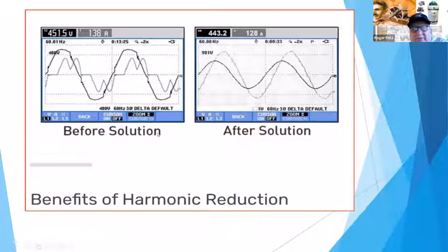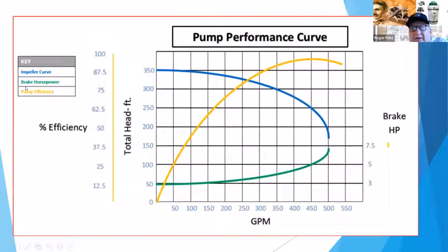This is an idea of looking at those waveforms before a filter. You can see that current waveform, then you can see the current waveform after we've cleaned it up. All that's happening is that you can see there was 138 amps at 451.5 volts, so the power load used by the motor was quite a bit higher than here. When we got it all cleaned up, it was at 443 volts and 128 amps. That's almost a 10 or 15 percent difference in power reduction going out to that motor, which all goes back to the circuit.